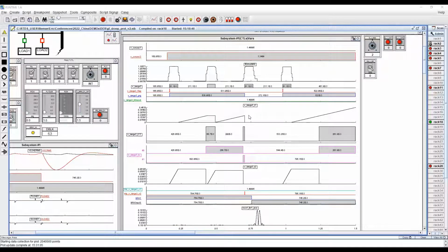The time monitoring the consecutive duration is reset here. The third disturbance came in before the time window for new sets expires. Therefore, a trip was asserted accordingly, followed by the auto reclose sequence as expected.